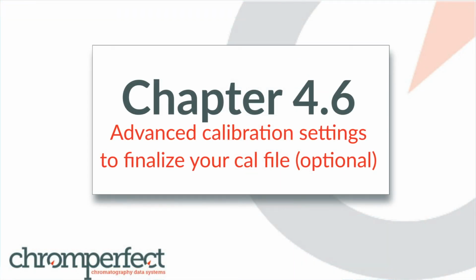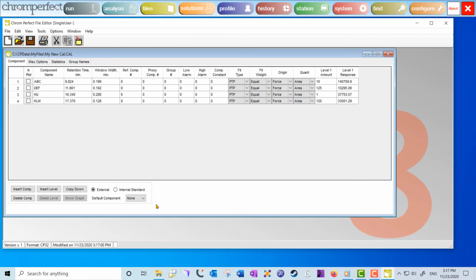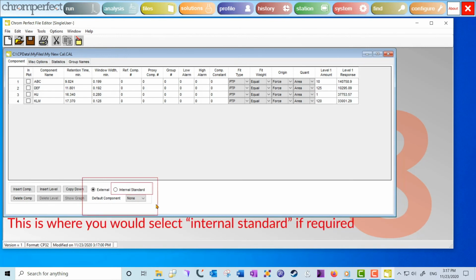Finalizing the calibration file. You may need to open your cal file in the editor to make additional changes so it is fit for purpose. A new calibration file will list all the named components, the retention times of those components, the area or height distinction, and a single calibration level with an amount and a response. All other fields will be in default condition, including the settings at the bottom of the Component tab.